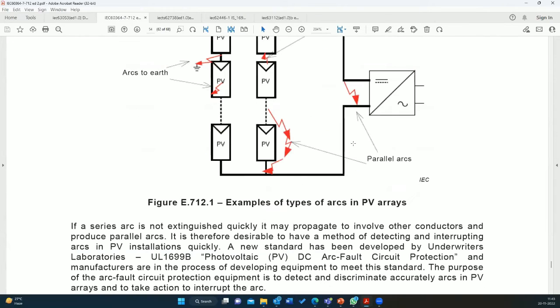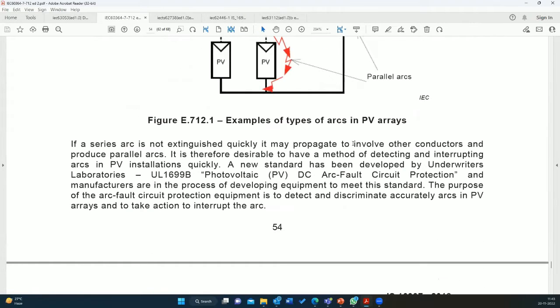So now I hope you understood the seriousness of the subject. I am just showing the standard to inform you that the situation in DC is not like the AC side. We have to apply separate or special protective measures. For example, for series arcs in an AC system, we have the arc fault detection device, AFDD, which is recommended, for example, in bedrooms, wiring in explosive areas, and so on, whereas that kind of device is not available for DC application.